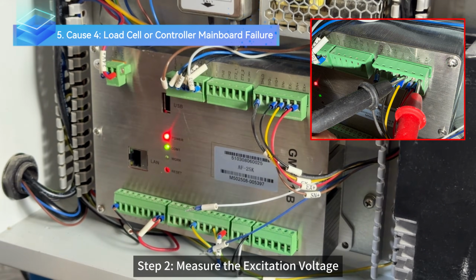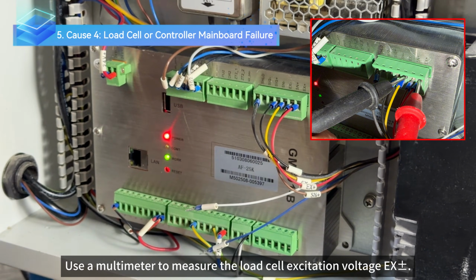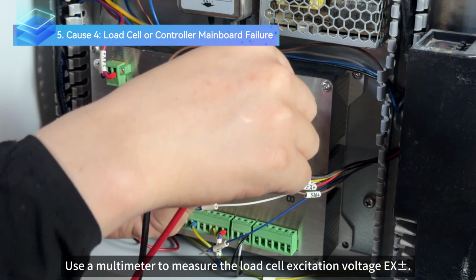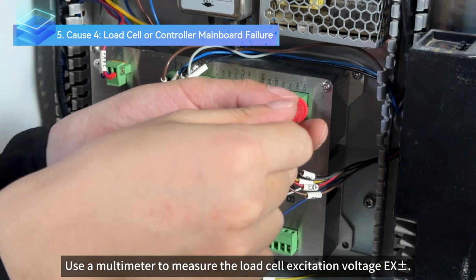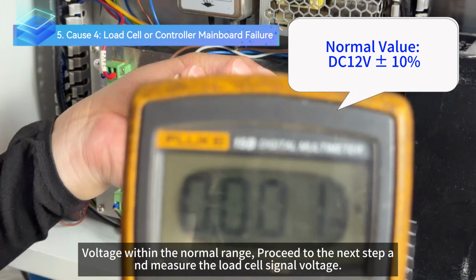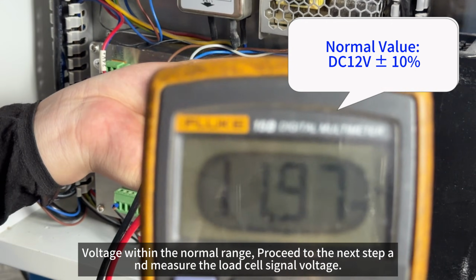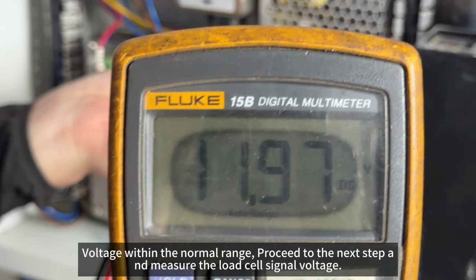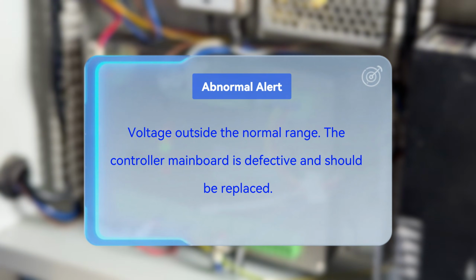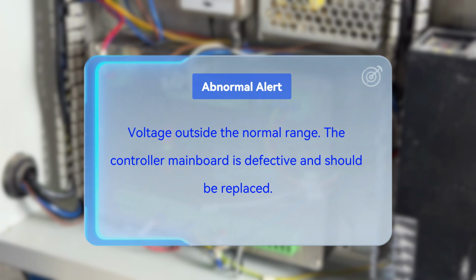Step 2. Measure the excitation voltage. Use a multimeter to measure the load cell excitation voltage, EX plus and minus. Voltage within the normal range: proceed to the next step and measure the load cell signal voltage. Voltage outside the normal range: the controller mainboard is defective and should be replaced.